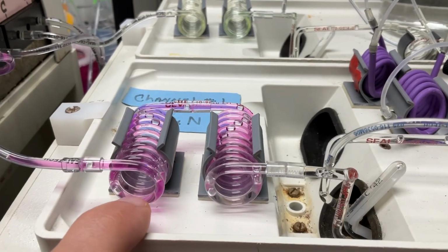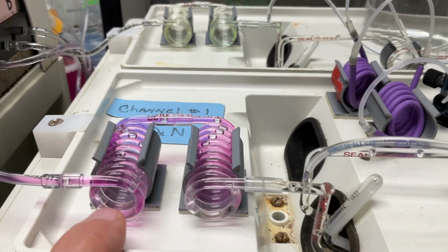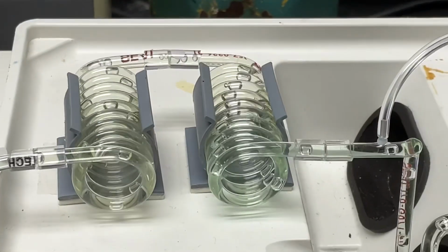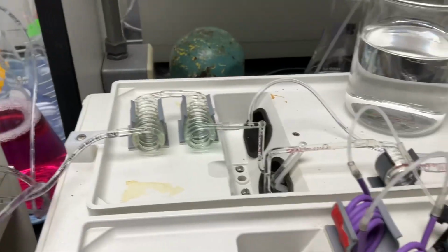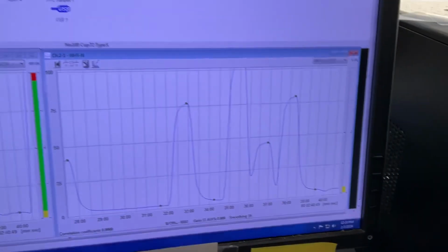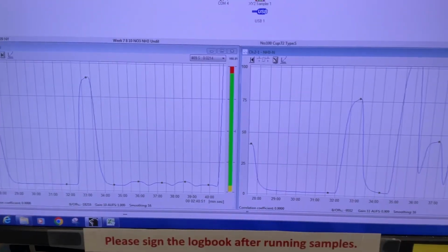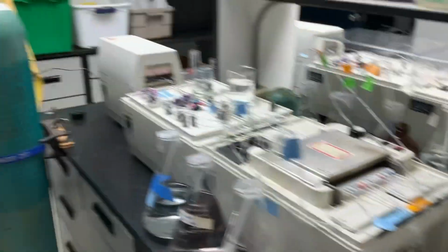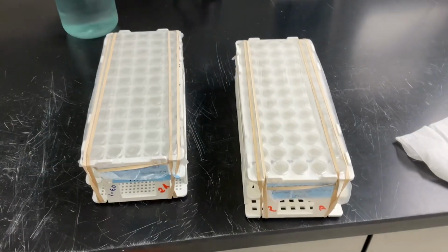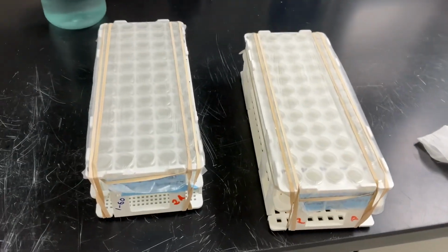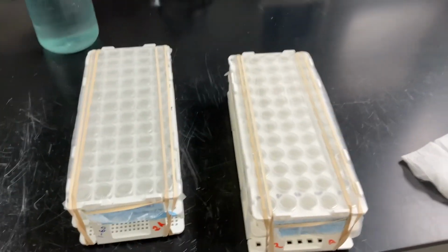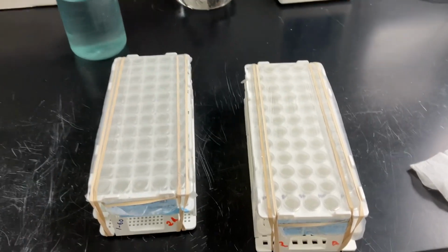And if the pink is too strong or too dark, the machine just gets saturated and maxes out, much like ammonium does at a point above 8 ppm ammonium. So you can see here, these are actually going above the detection threshold, and that red bar right there is telling me that this incoming peak for that high pink sample we just saw is going to be way off the charts.